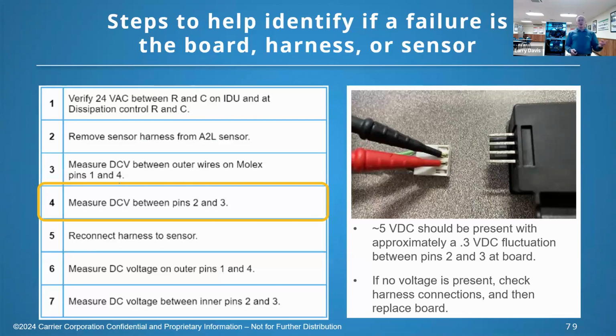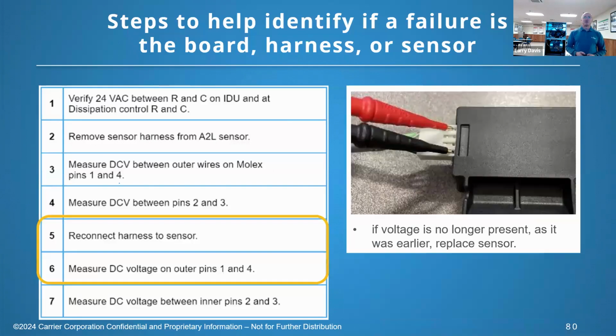So it's sending that out looking for a feedback signal. And if it's not there, then check again at the board. Make sure you don't have a break in the harness. If you're not seeing it there, then the board's bad. Reconnect the sensor. Our 5 volts on the outer pins should not go away. It should still stay there. If we lose our 5 volts DC, we have a shorted or a failed sensor.